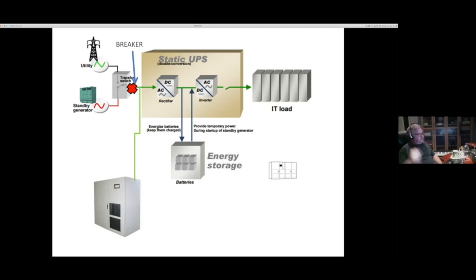They tried to pump it up and reconnect the breaker. You have to pump these things up, then push the button. It's like the Jurassic Park metaphor where you pump the breaker up and you see the lights go - well, it's not quite that dramatic, but pretty similar. You have to pump it up and then push a button. They tried twice and the breaker would not come back, which is obviously a big problem.